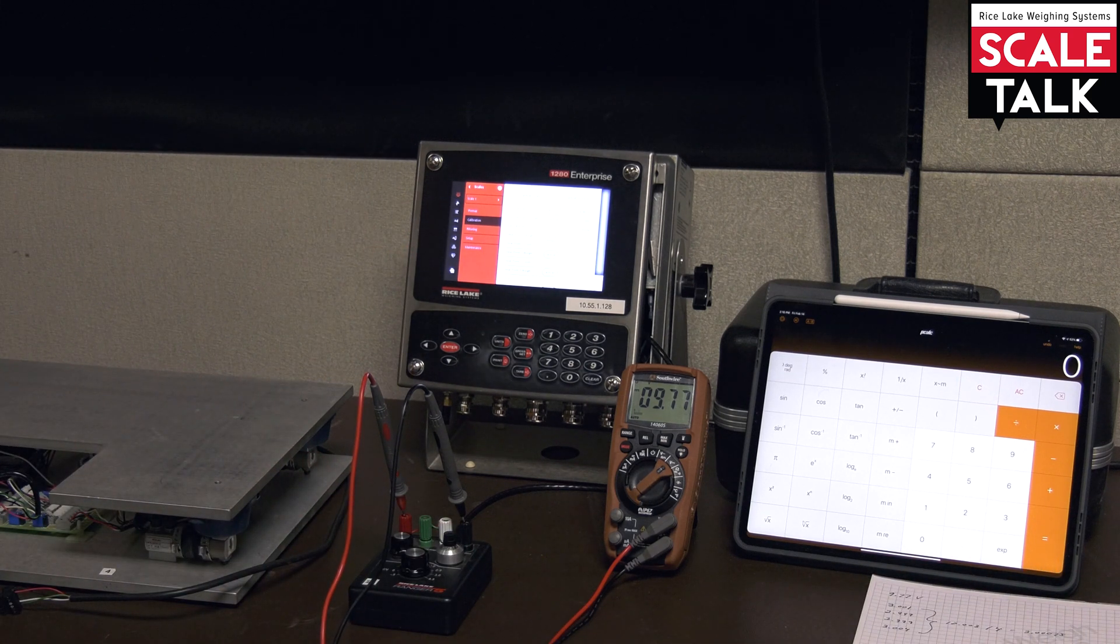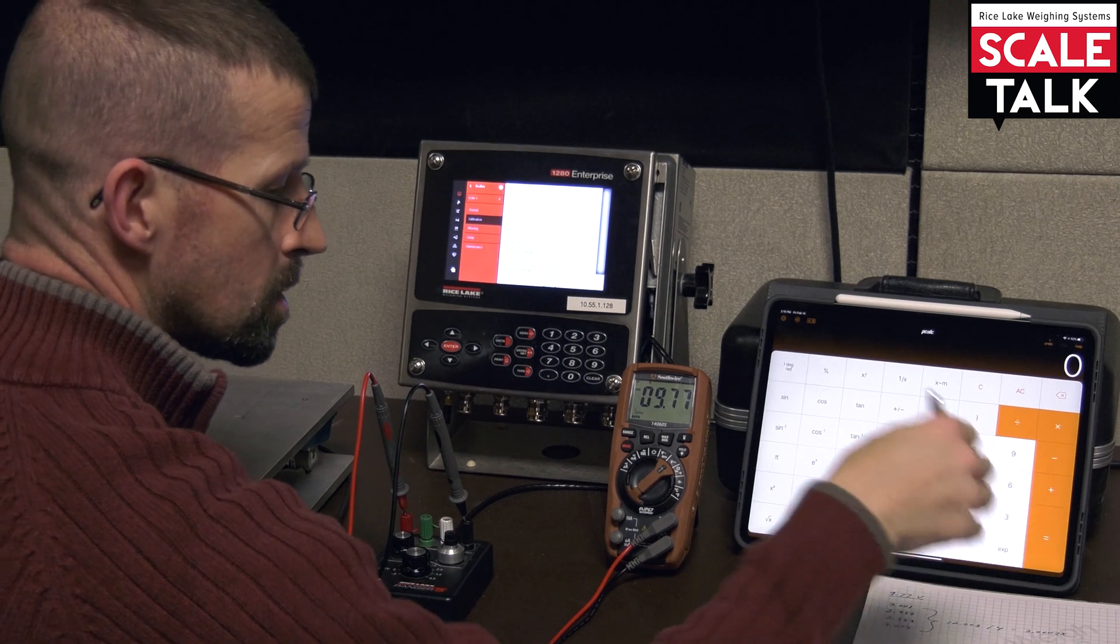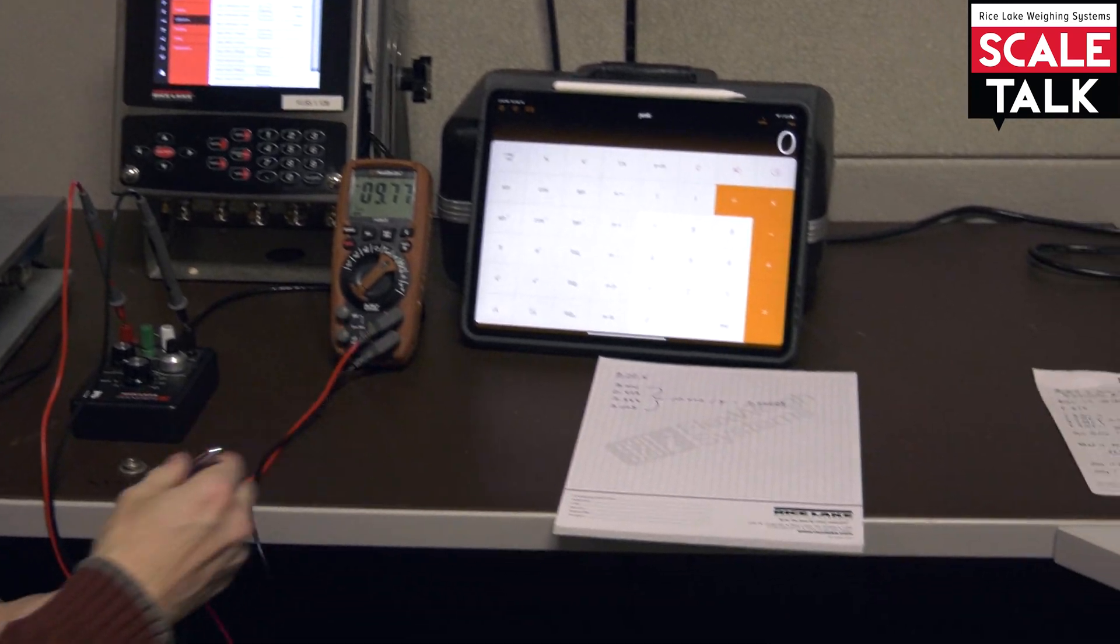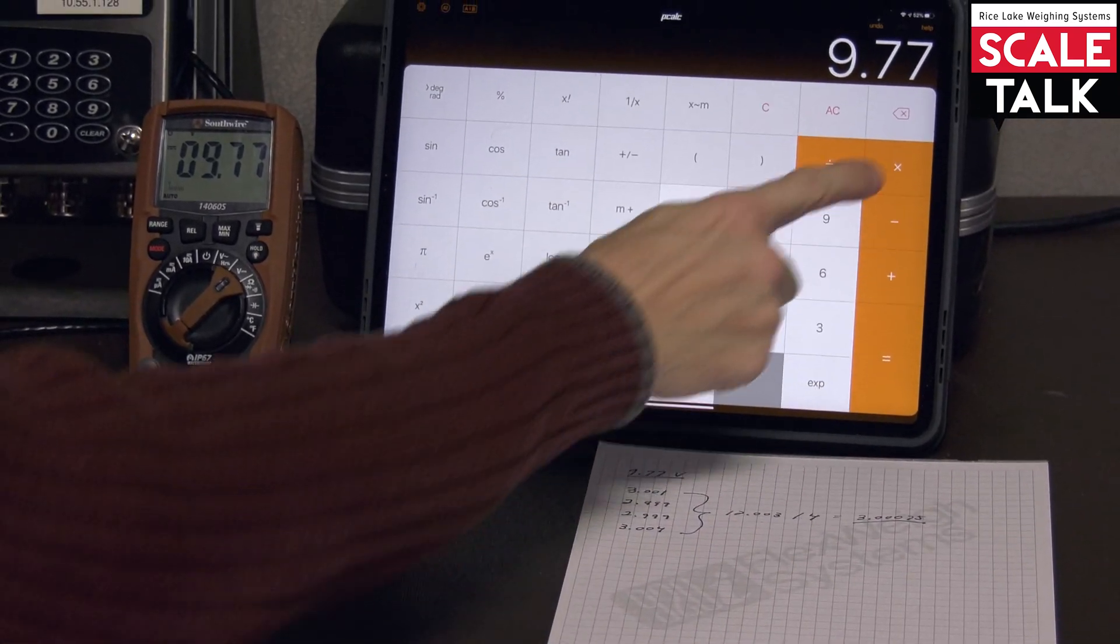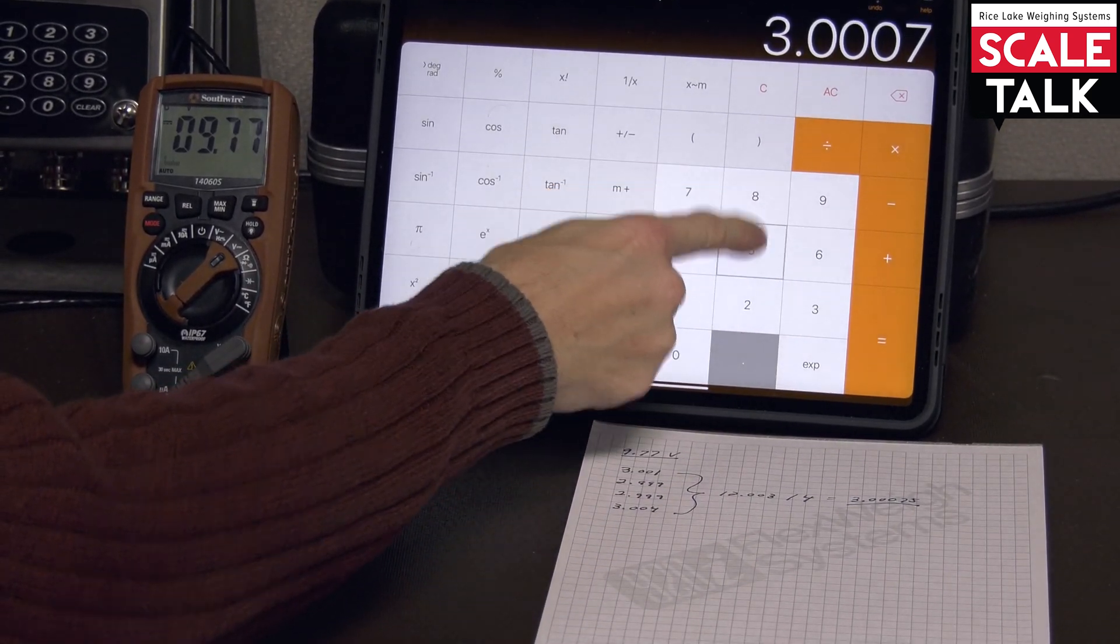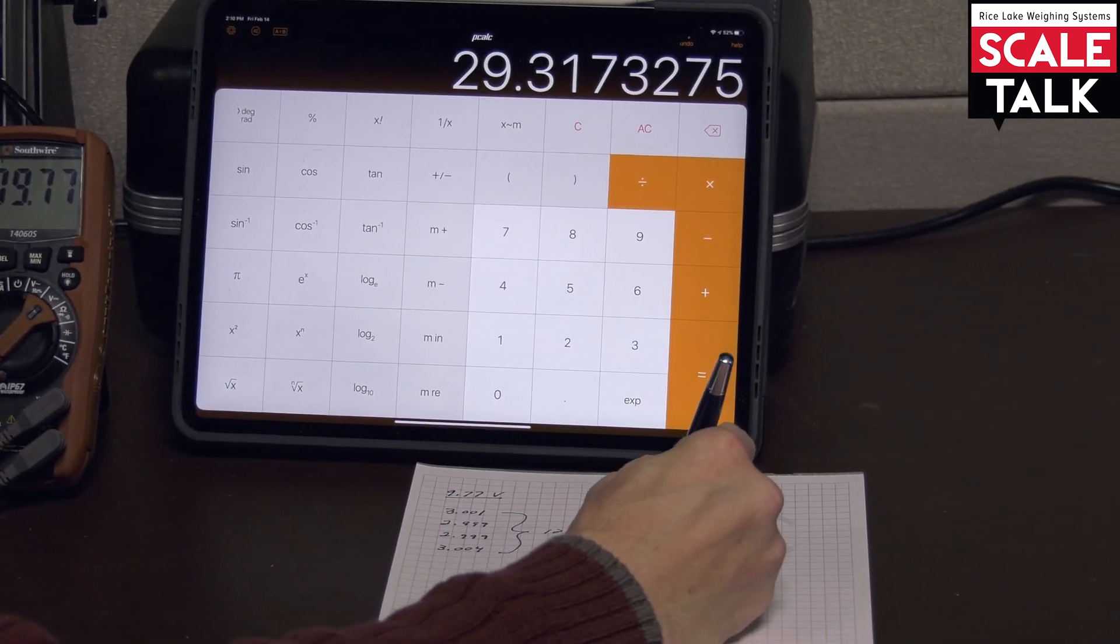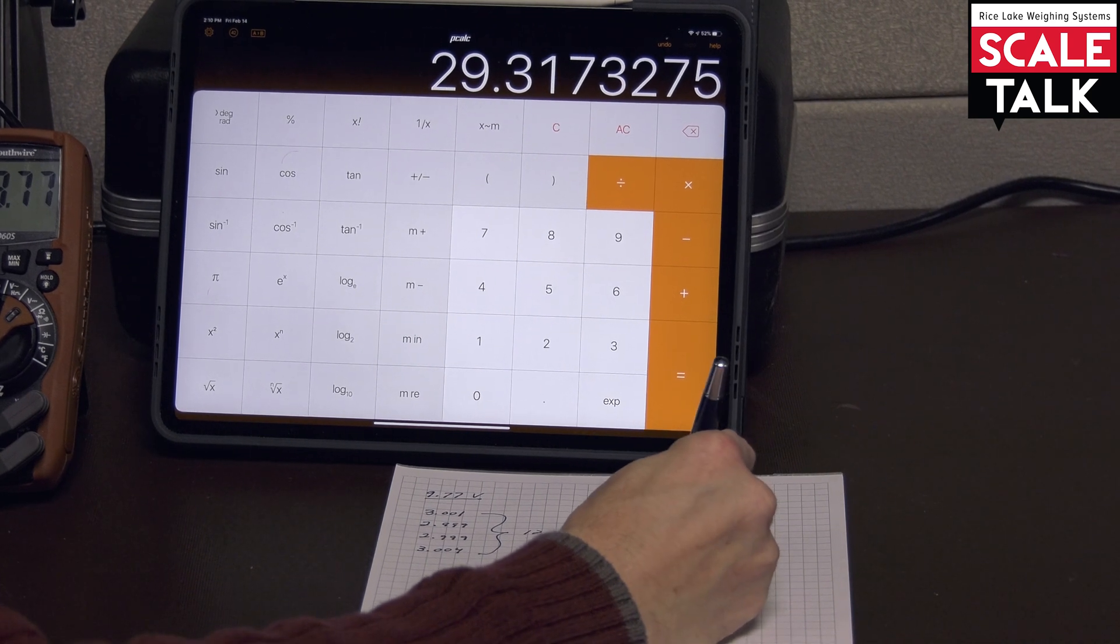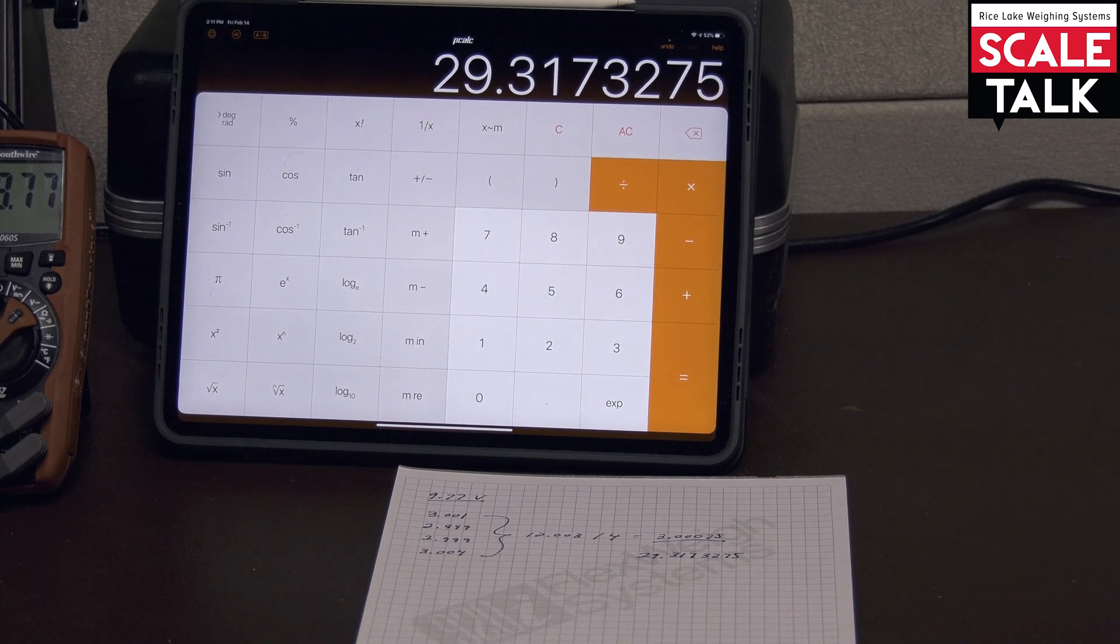Now to determine what the full scale capacity is of the system we would need to take the product of these two numbers here, my excitation and my average. So let's take a look at that. If we do 9.77 and multiply that by our 3.00075, that gives me a value of 29.3173275. I'll just write all those numbers down.